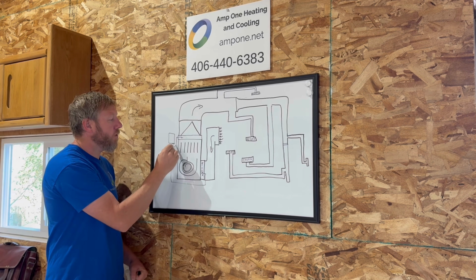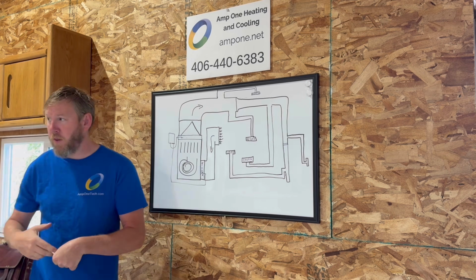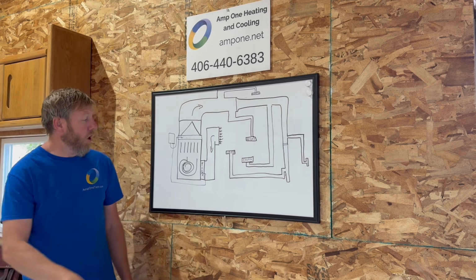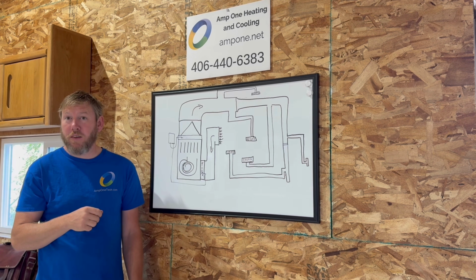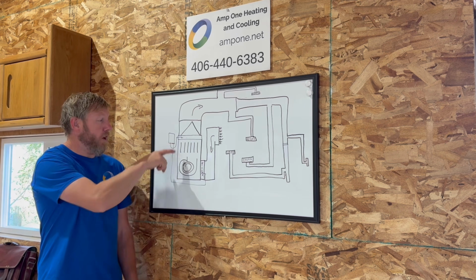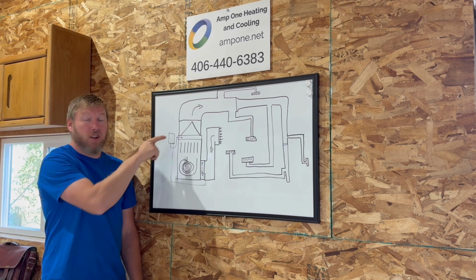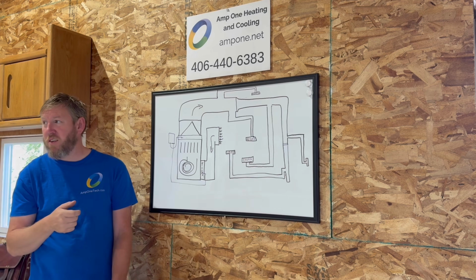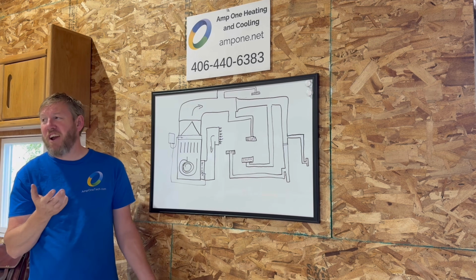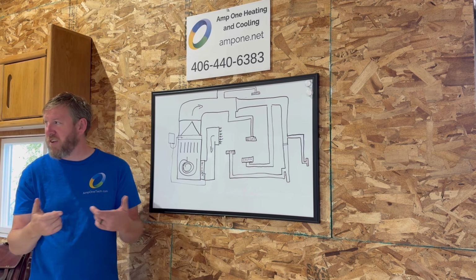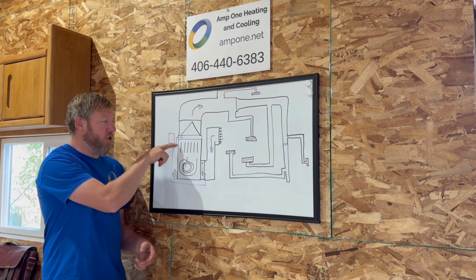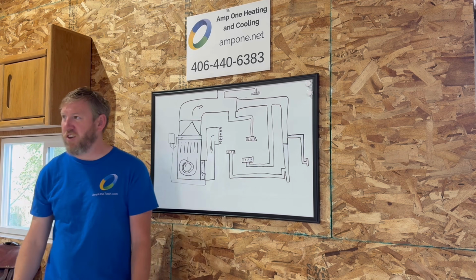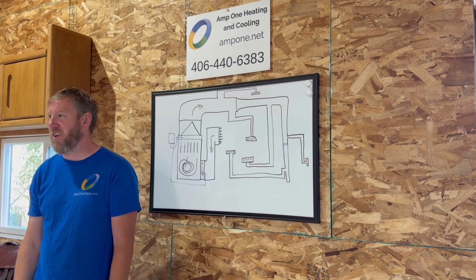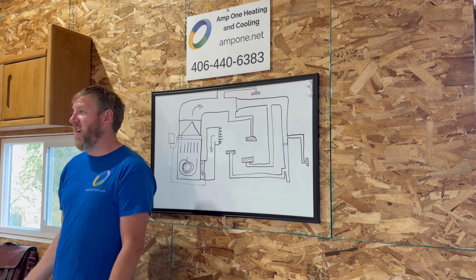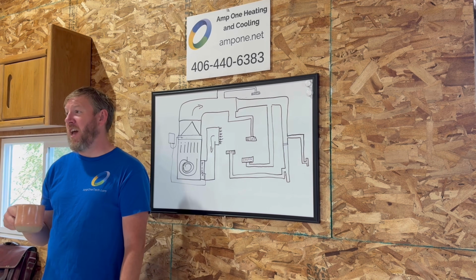Just because it's kind of sketchy screwing in right next to the coil. Yeah, right next to your heat exchanger. Because if you hit one of them, you're like, well, there goes all my refrigerant, or now I have a cracked heat exchanger. A lot of times you go right into the side of the furnace, and it's scary. That's why you probably want to use a step bit to do it, so you're not punching a hole through your heat exchanger, because then you're changing the furnace. It always sketches me out. But don't do that, because that's on my dime, and I would not be happy changing out a furnace.